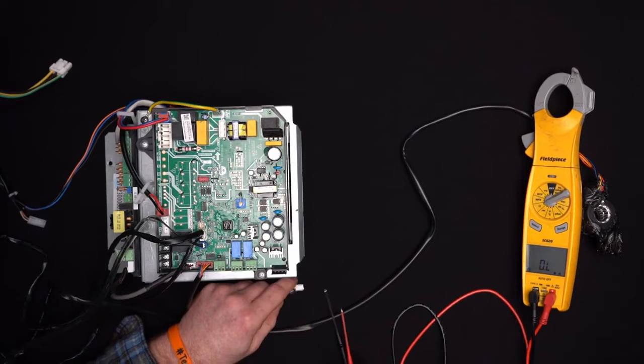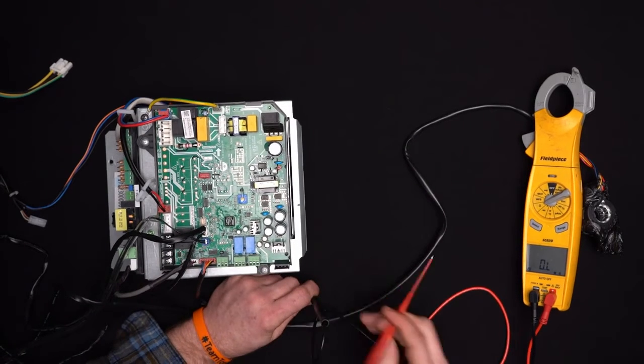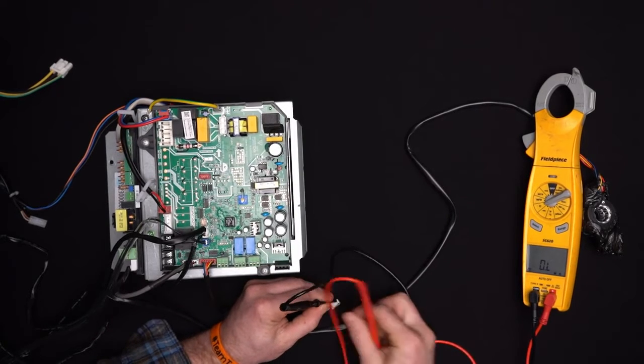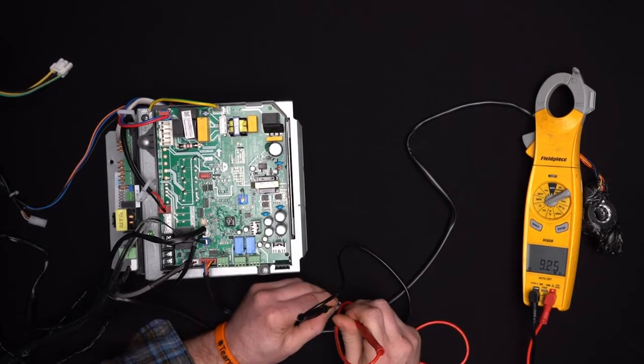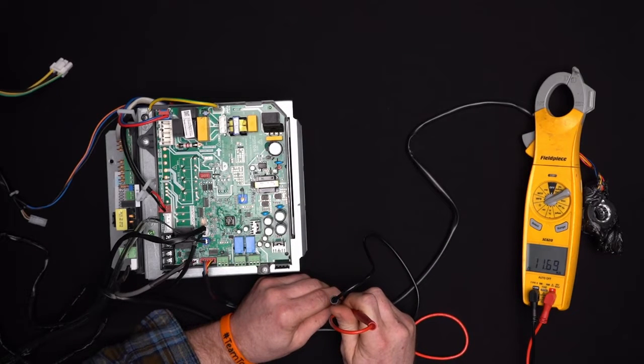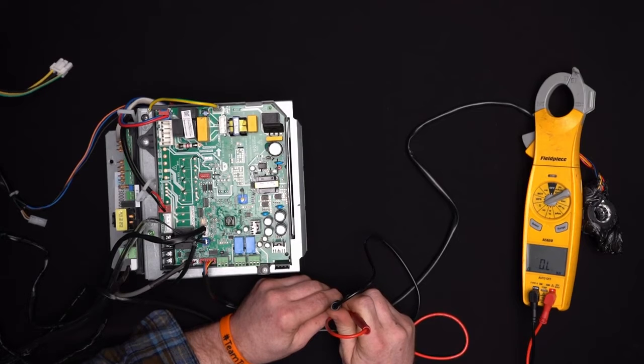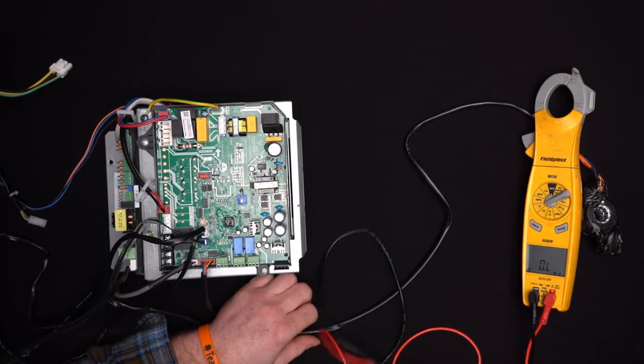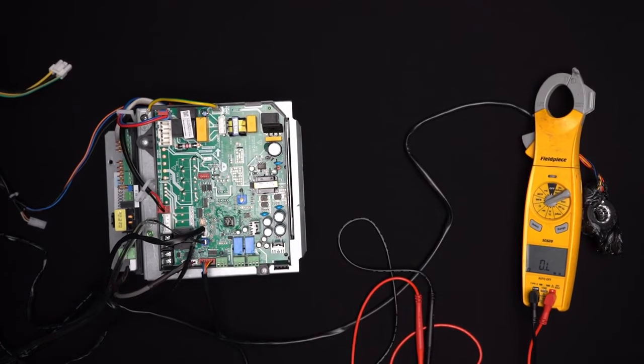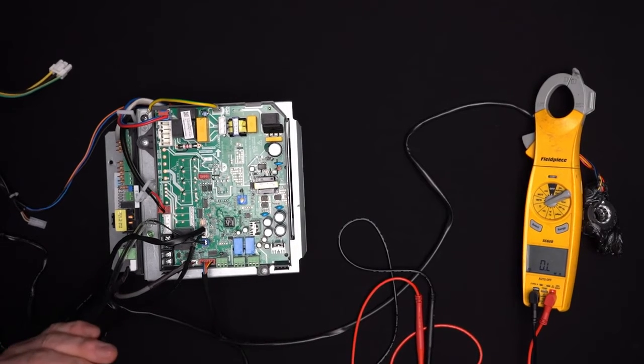And I'm going to check across these two pins. And you can see on this thermistor, I'm getting 11.69K ohms. So you would match that with a chart for the ohms. It's a 10K two, and that would give you what the temperature is for what the ohms are.